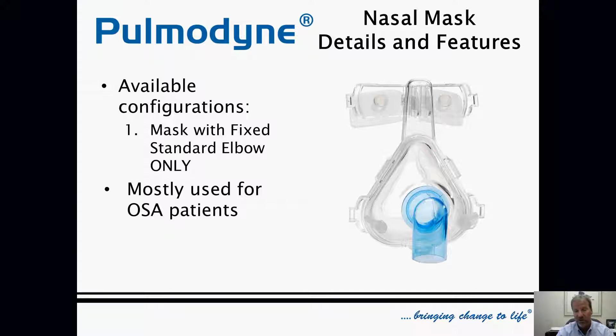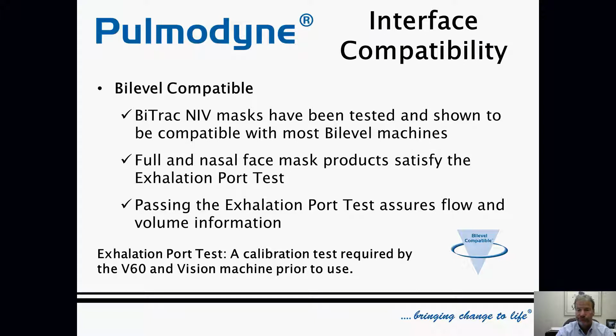So our BiTrac bi-level mask, we have a big selection of different things. I don't even know what that really says. Let's see, managing excessive air leaks. It's interesting, none of these masks need to seal to the point that they don't have a leak. So they all are designed to leak. So the pressure or the flow that these BiPAP and CPAP machines deliver is always more flow than the patient needs, and as a result, the devices are set up to leak.